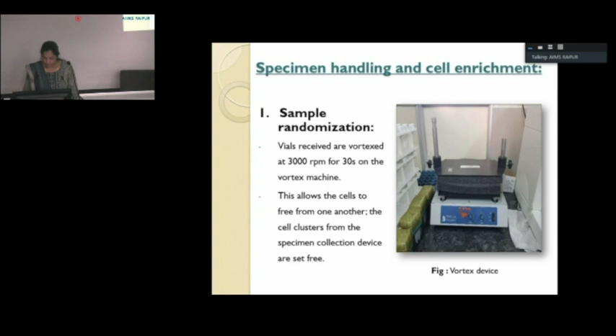The next step is mixing and layering. Here the other component apart from the vortex is the PrepMate of the SurePath. The PrepMate system is loaded with a plunger, a sample vial and a centrifuge tube containing 4 ml of the density gradient. This density gradient is a polysaccharide solution with sodium azide as a preservative. A single specimen rack holds 12 samples at a time. Thus 4 specimen racks are there for the machine, so at a time we can process 48 samples.